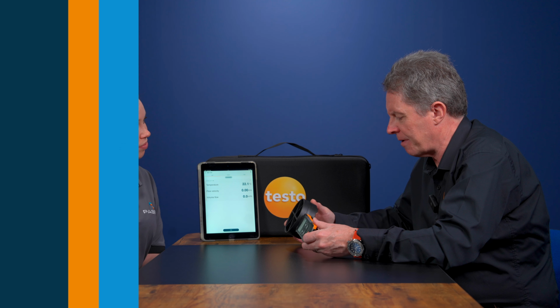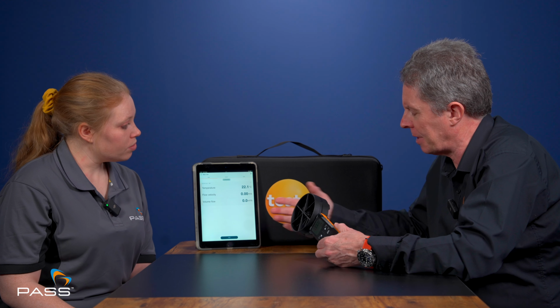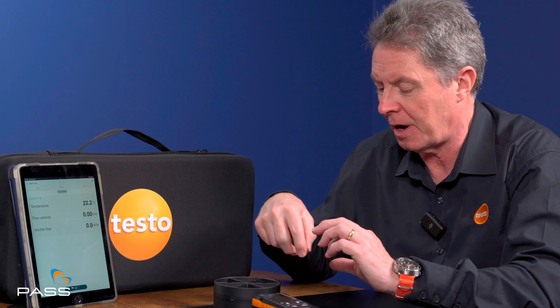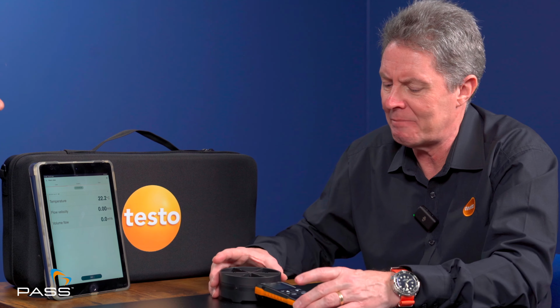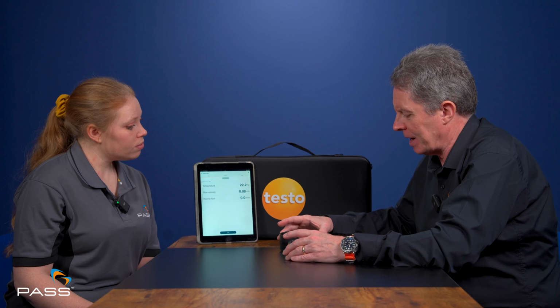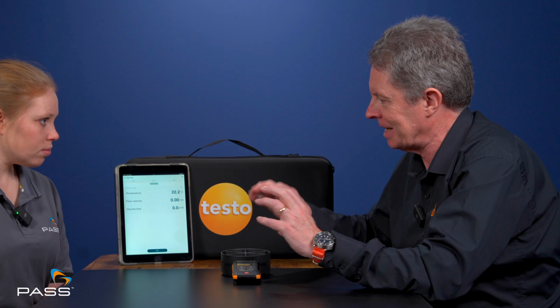Is there anything else you want us to know about the Testo 417? Yeah, something that's very fresh and new - we've got an application within the app itself. One of the things we're finding, particularly on commercial ventilation systems, is if you've got lots of ventilation outlets or fresh air inlets, you have to balance the system. There's an aspect where it's not just measuring at one point, you're measuring at multiple points and then balancing the airflow to make sure each room is getting the correct amount of air exchange. This can be very time consuming to do these measurements manually.